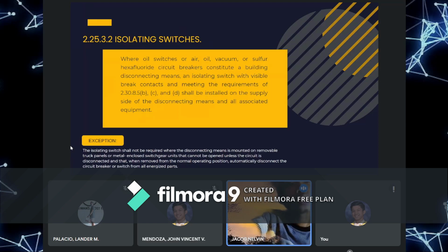Sabi, the isolating switch shall not be required where the disconnecting means is mounted on removable truck panels or metal enclosed switchgear units that cannot be opened unless the circuit is disconnected, and that, when removed from the normal operating position, automatically disconnect the circuit breaker or switch from all energized parts. Ano ba itong mga tinatawag nating isolating switches na to?